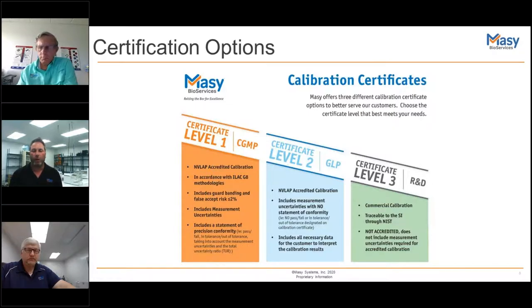As you can see, this is an accredited cal. It's in accordance with the mathematical principle on the previous slide. It includes the guard banding risk with false accepts, and has the uncertainties in the statement of conformity. As the blurb says, if I say a unit passes or fails, all aspects of the measurement are quantified in that result - it's not just a reporting of data.